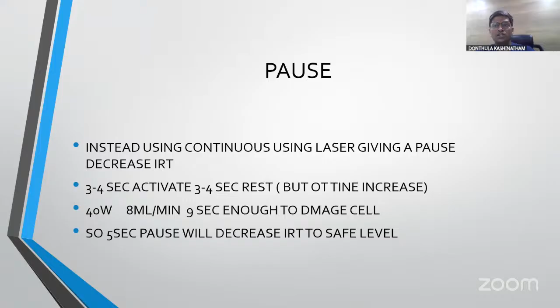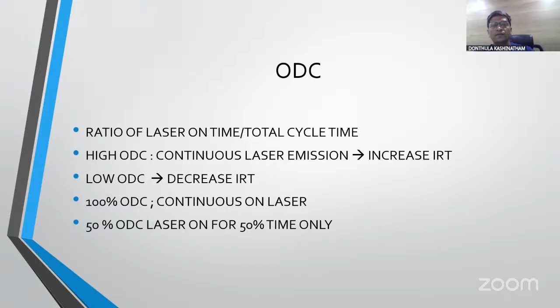If you want to use more energy, give a small pause. Take a small break when you are doing a procedure. Don't continuously keep hitting the pedal. This has been assessed as ODC. ODC of 100% means you are using the laser continuously, not raising your foot from the pedal. But if you use only 50% ODC, it means that out of one minute of lasing time, you are using only 50% of the laser throughout the cycle. So with ODC 50%, the complications will definitely come down. It is called the operator dependent cycle.